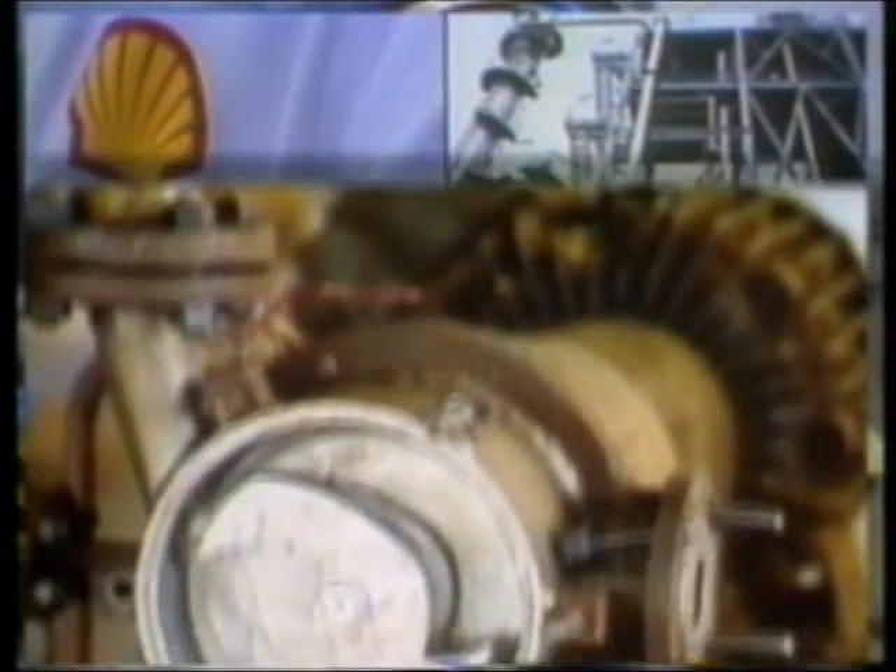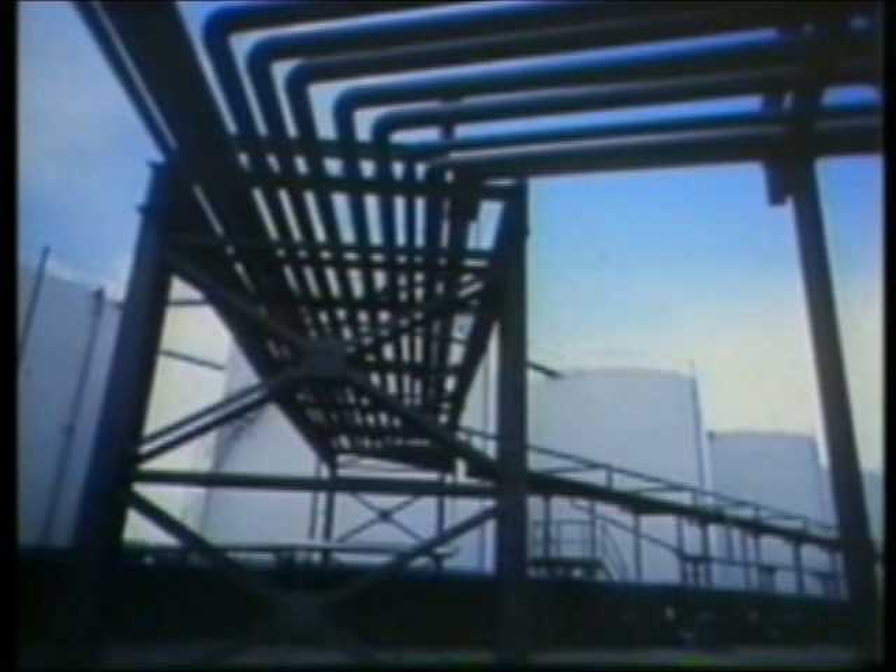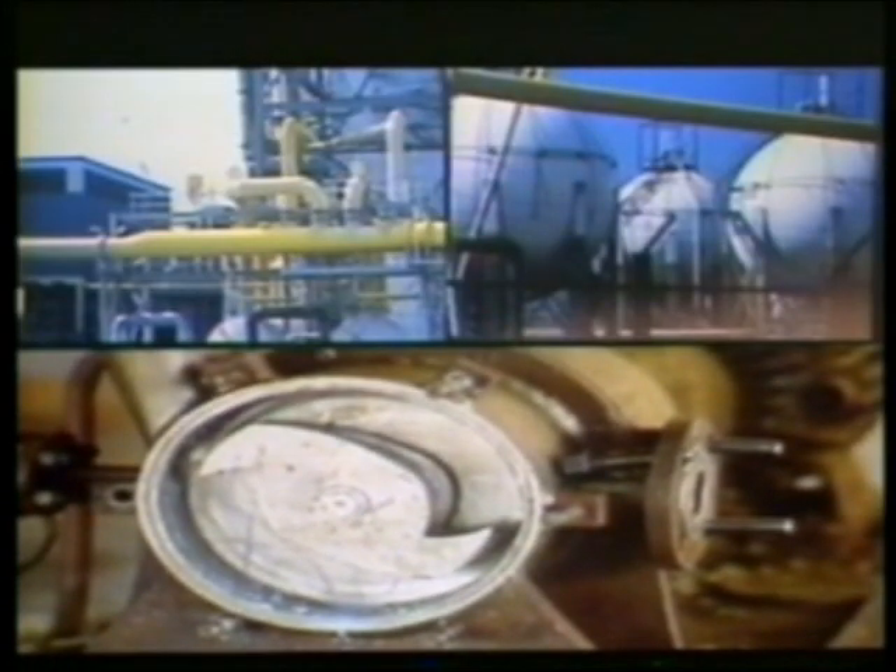This pump at Shell Pernis, transporting latex, had to be cleaned nearly every three weeks. Also, the mechanical seals had to be replaced each time. After a micropeening treatment — by now more than three years ago — the pump hasn't been out of service. Time and cost savings speak for themselves.